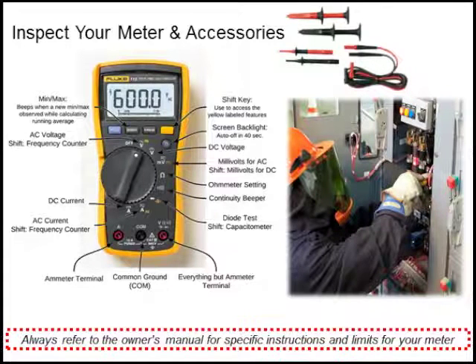Now we're ready to inspect our meter. When you inspect your meter, the first thing you want to check is to make sure that there's no damage to your leads, that the ports are in good shape, your indicator window and fusing is all in good working condition. Never use a damaged tool. And don't replace quality leads with cheap stuff you buy off the shelf.